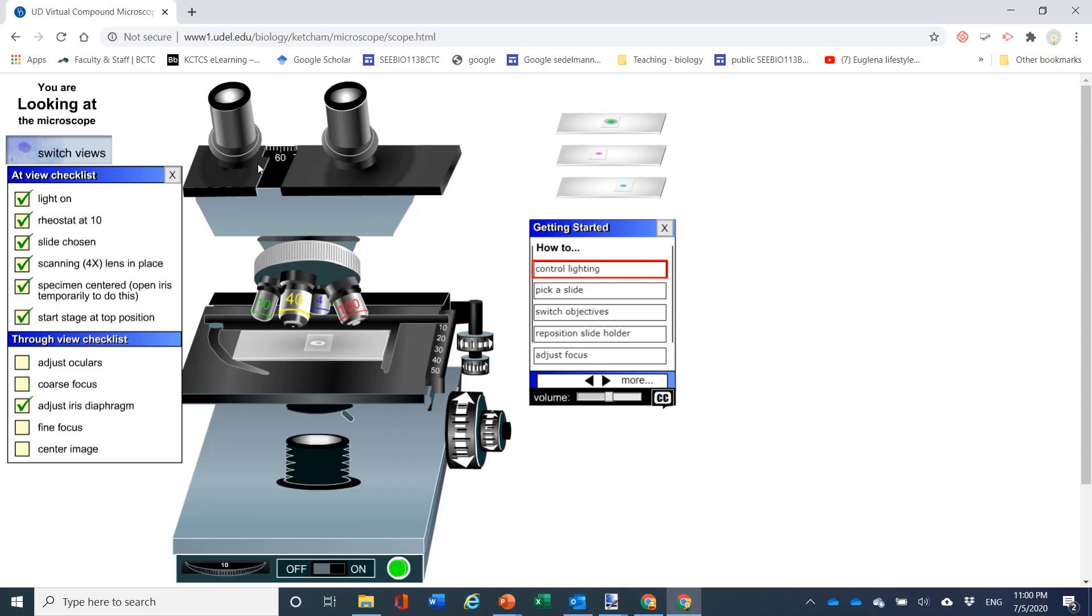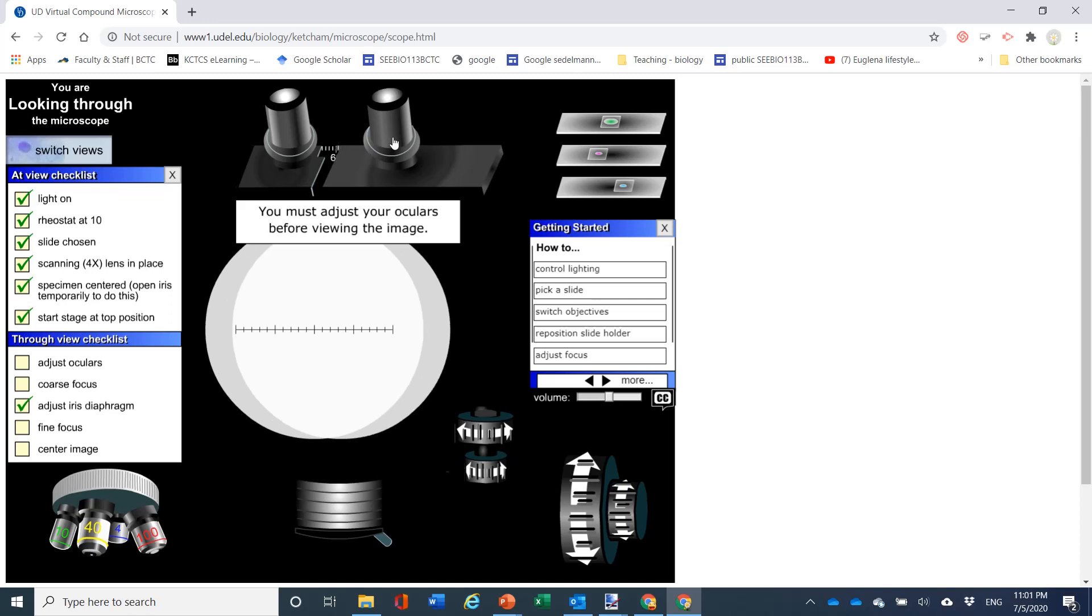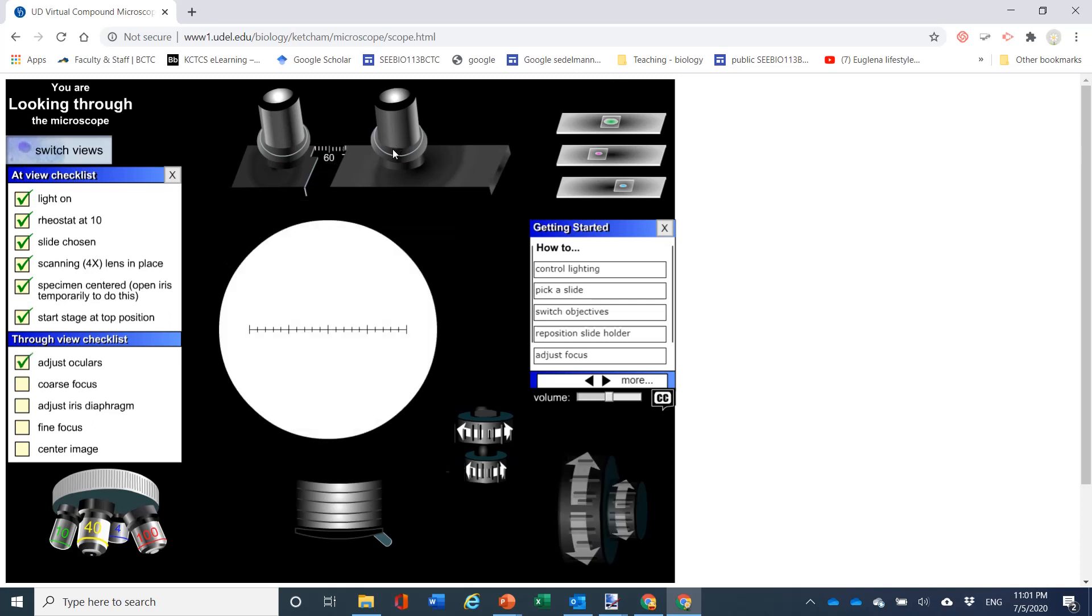Now you want to adjust the oculars and for this you have to switch the views. But in real life, what you're going to do is, this is one of the things that students usually have the biggest amount of problem with, is trying to see this view so you look at it with two eyes. What you're going to see is you're going to see two overlapping images. And as you move these closer together or further apart, you get at some point to the point that it looks like just one image. And that's what you want.